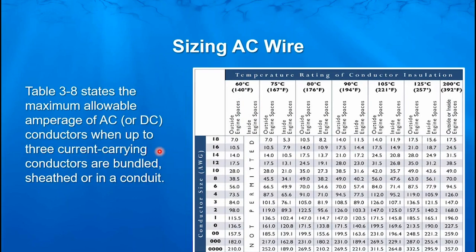If we go to Table 3-8 — which is for up to three current-carrying conductors — using the same 10 gauge at 105°C: because we've added two other current-carrying conductors, we're now only allowed to put 42 amps instead of 60 through the wire outside engine spaces, and only 35 amps inside engine spaces. As you can imagine, the subsequent tables I mentioned — the more conductors you add together — the lower the allowable amperage is going to go for that wire included with many other cables.